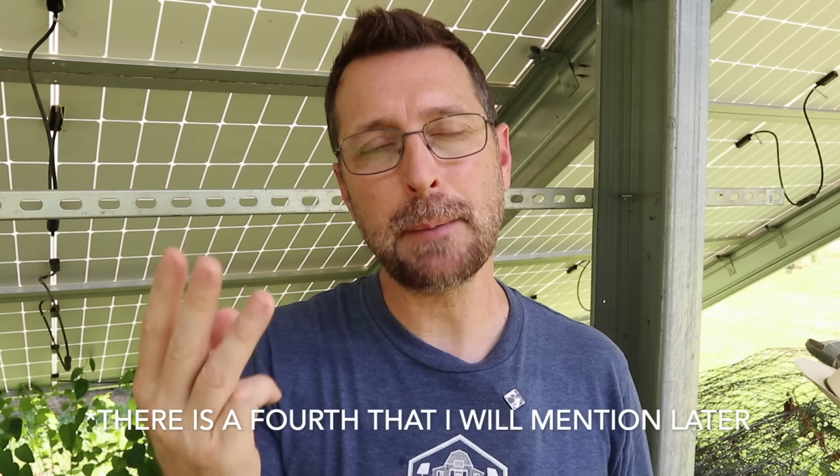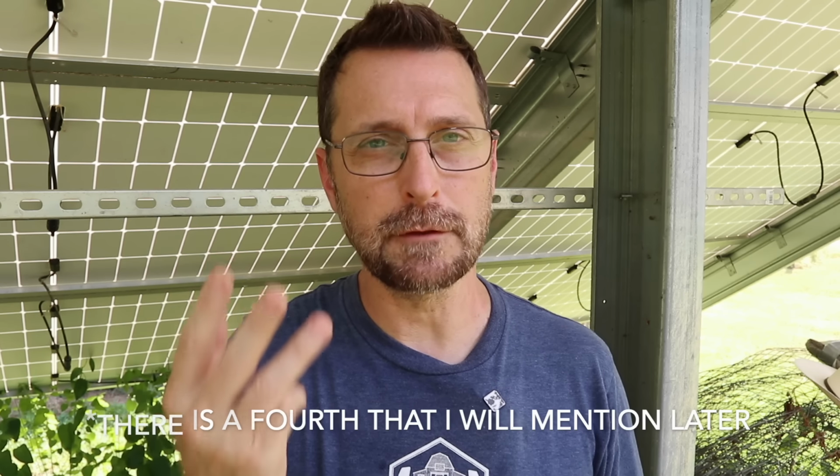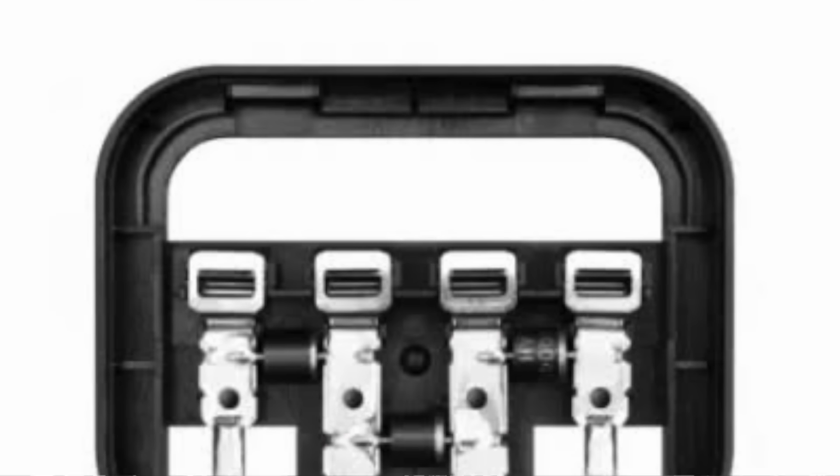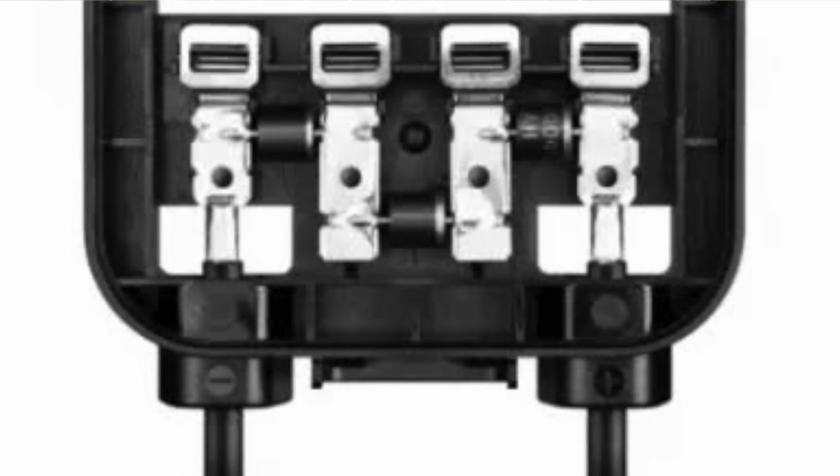So we need to look for a bad connection, a cut wire that's short-circuiting, or there's a third option, and that is a bypass diode in one of the panels. Those bypass diodes will cause fluctuating current, but the voltage relatively stays the same. And it's usually when you have a damaged or failing diode in the panels that it will do that.